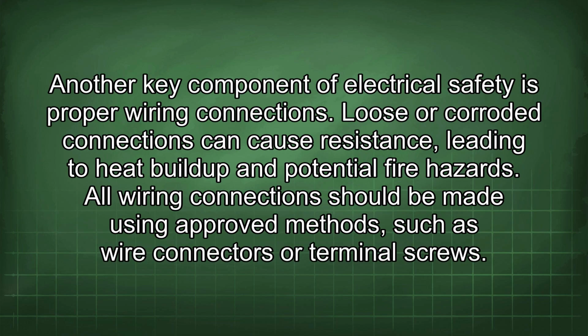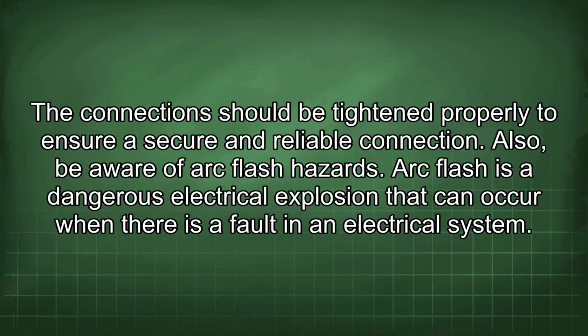Another key component of electrical safety is proper wiring connections. Loose or corroded connections can cause resistance, leading to heat buildup and potential fire hazards. All wiring connections should be made using approved methods, such as wire connectors or terminal screws. The connections should be tightened properly to ensure a secure and reliable connection. Also, be aware of arc flash hazards.